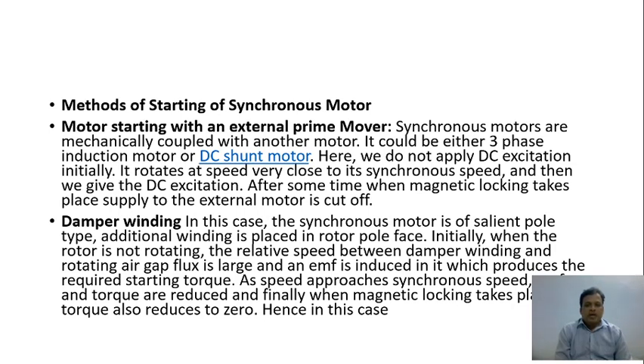So we do not apply DC excitation initially, and it rotates at a speed very close to the synchronous speed. And then, after rotating at very close to synchronous speed, when the DC excitation is given, after some time when magnetic locking takes place, the supply to the external motor is cut off. Like this, we achieve the starting of the synchronous motor.